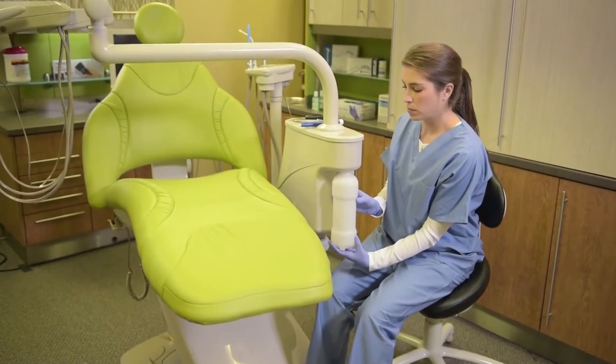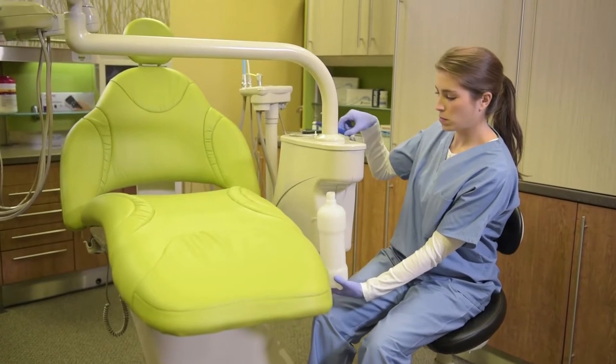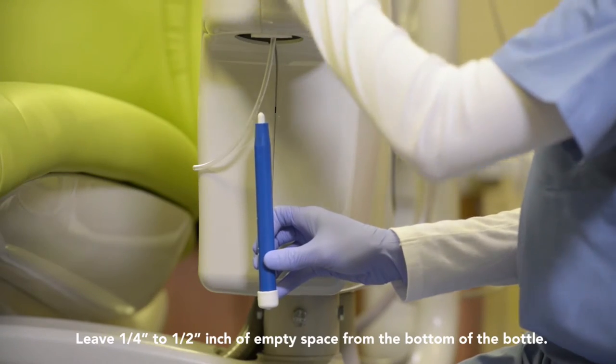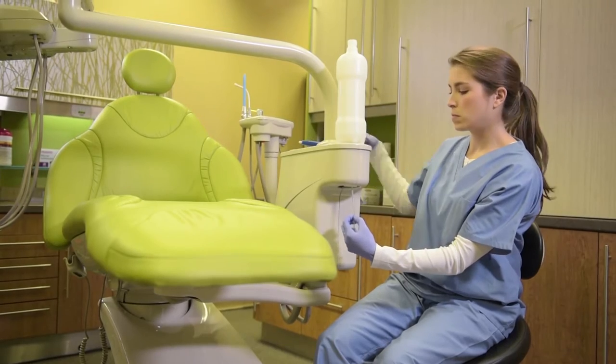First, remove the dental unit's water bottle to reveal the bottle pickup tube. Align the bottle alongside the pickup tube in order to ensure your DentaPure cartridge can attach to the pickup tube with enough space to fit inside the bottle.